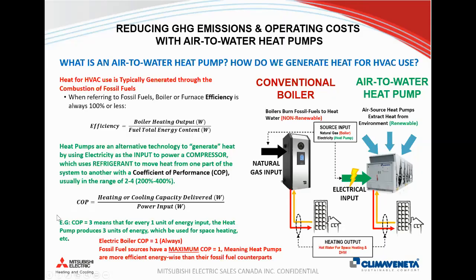I've said this a couple of times throughout the presentation: COP. This stands for coefficient of performance. Coefficient of performance is basically a metric where you look at the heating or cooling capacity delivered from a machine and divide it by the power input. Typically, at nominal conditions for air-to-water heat pumps, the coefficient of performance will be 3. This means that for 1 unit of electricity or energy you put into the machine, you get 3 units of thermal heat out from it. So if we're comparing efficiency of a boiler from a pure energy point of view, a heat pump at nominal conditions with a COP of 3 will be 3 times more efficient than its natural gas counterpart.